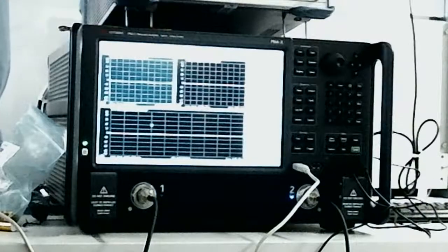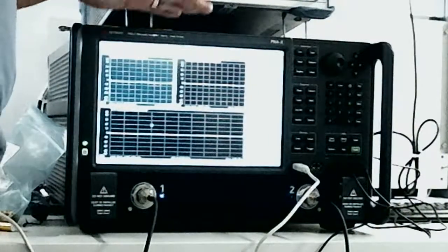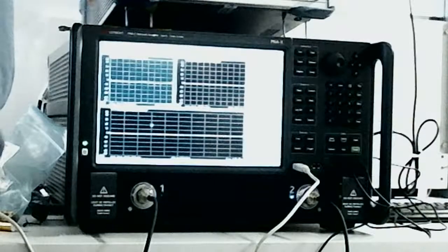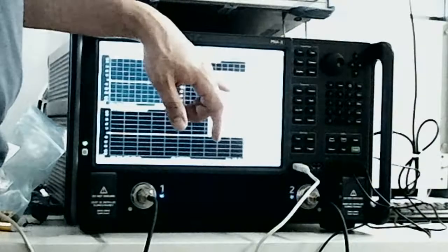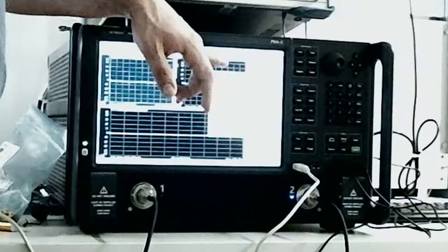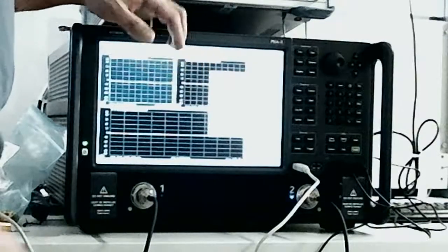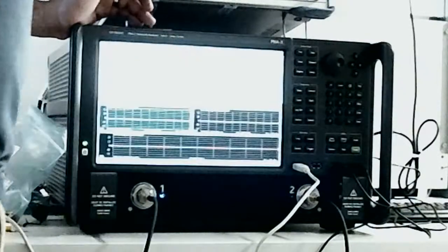Okay. So what we do is under cal. You remember last time, what I did is I just did smart cal, right? And what that does is calibrate whatever active channel you have. What you can do under other cals here, instead of the smart cal, is activate something called cal all. What this does is it calibrates any number of channels you want.